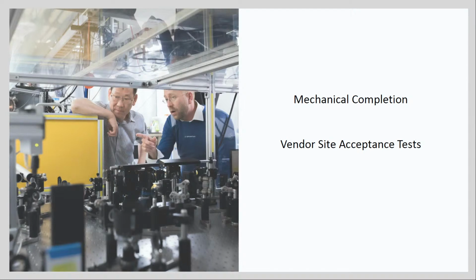Now we'll go through some of the typical pre-commissioning activities in the next few slides here. So some of the first activities, or an example of pre-commissioning, could be vendor site acceptance testing, or vendor SAT. This is very similar to factory acceptance test, with the exception that now the testing is done on site. So the vendor may have done a certain set of tests in the factory. They'll typically come to site and do some of those tests or all of those tests again on site. This confirms that there was no damage during shipping or installation. Similar tests could be performed as were done in the factory.